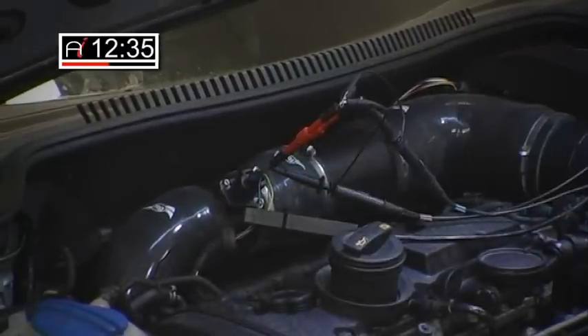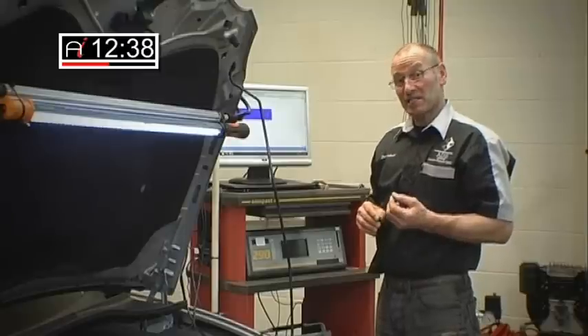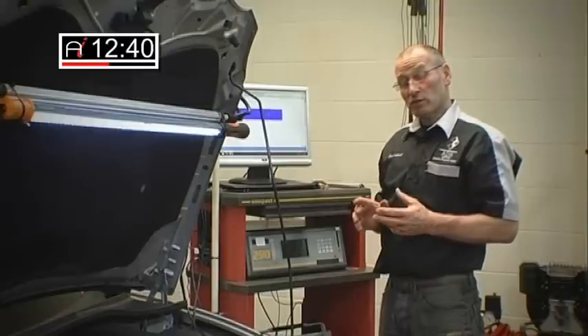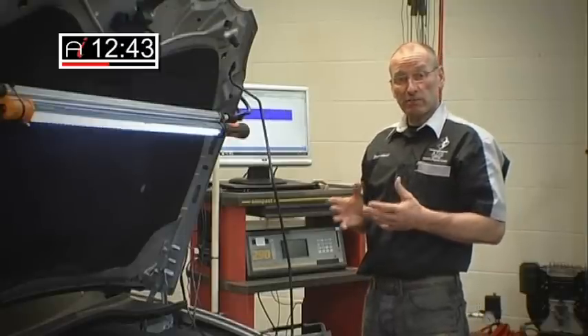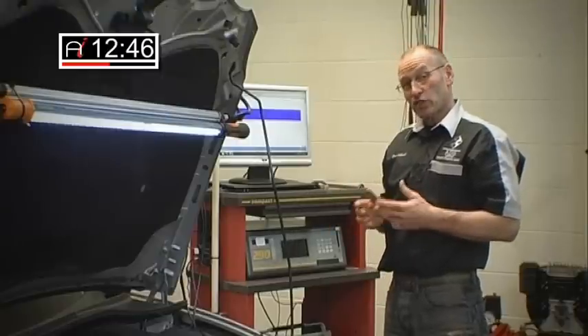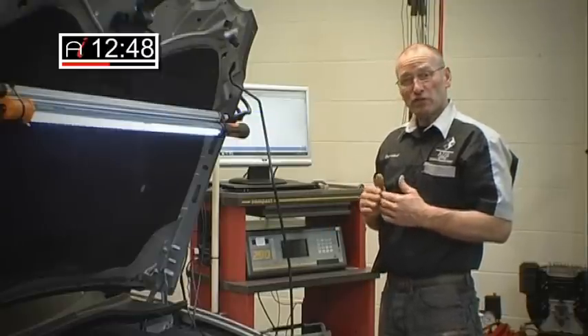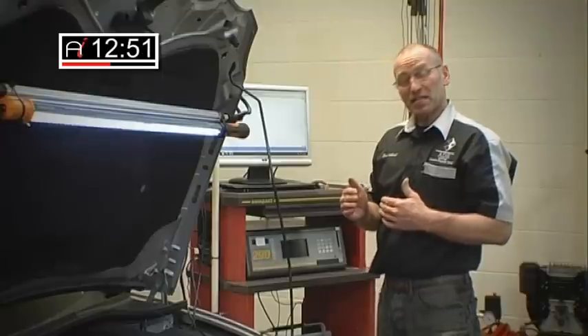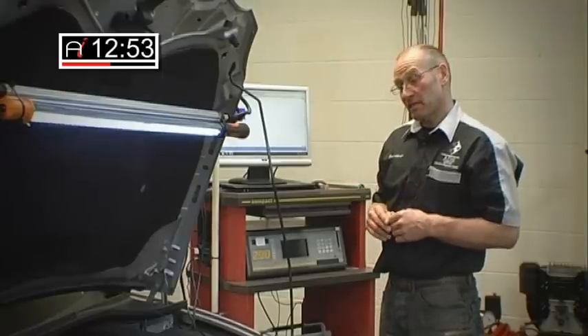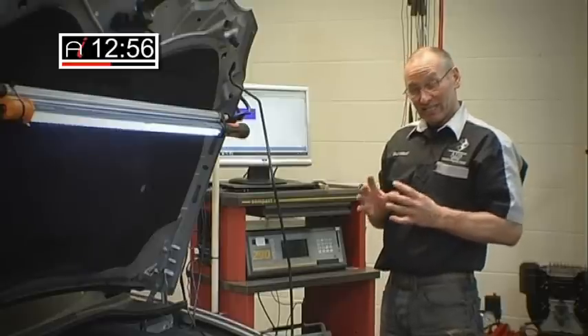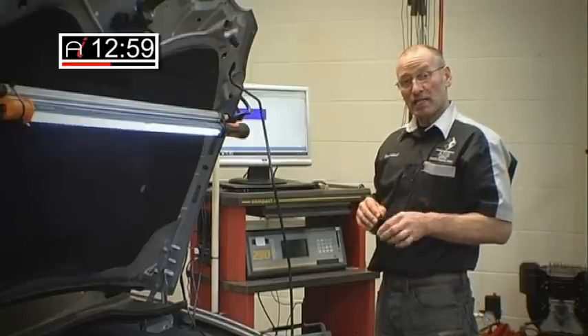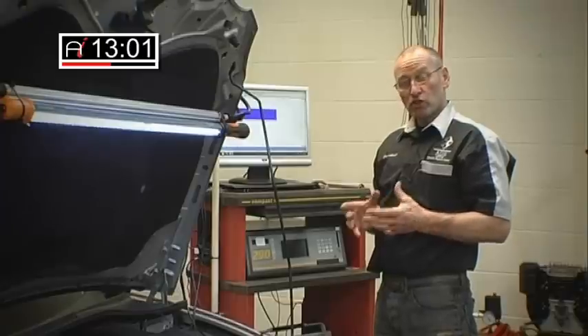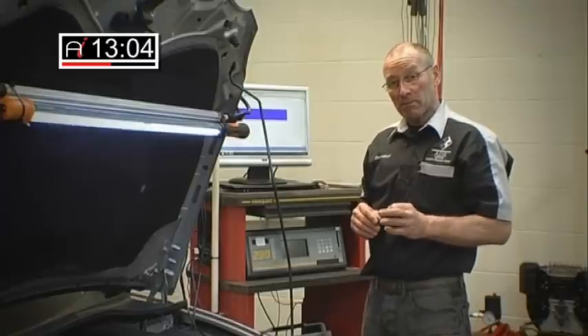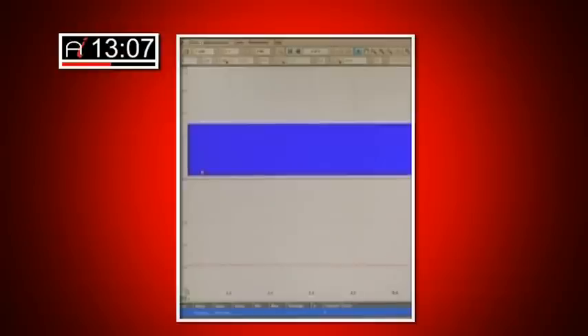The next thing we need to assess or estimate is the attenuation or sensitivity of the clamp. Now we've found from research and development and some experience that a 2-volt range gives us enough image size for the entire output range of the air mass meter. The conversion rate is every 10 millivolts is 1 milliamp. So 2 volts becomes 200 milliamps of current flow. So I'm going to now select the green channel, channel 3, at a 2-volt range.